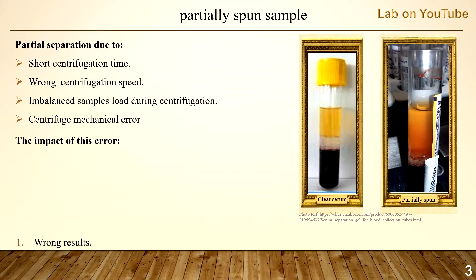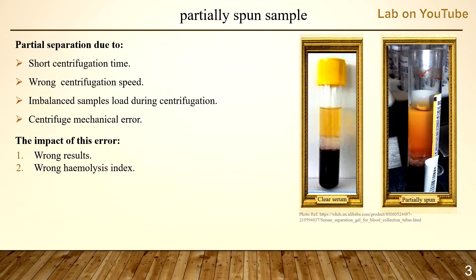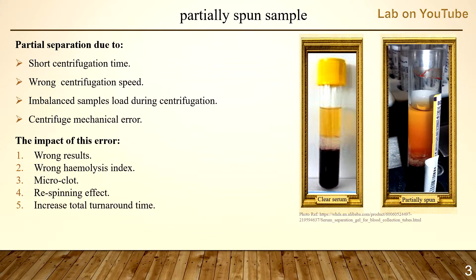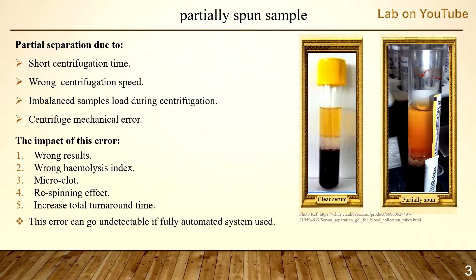The impact of this error can cause wrong results, wrong hemolysis index, micro clot, re-spinning effect, and increased total turnaround time. Note: this error can go undetected if a fully automated system is used.